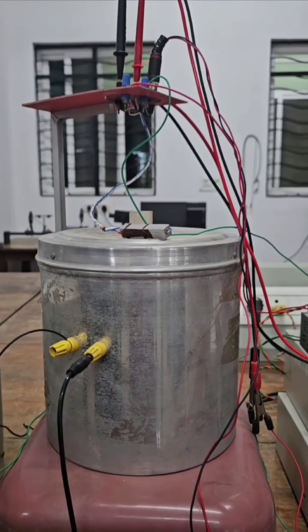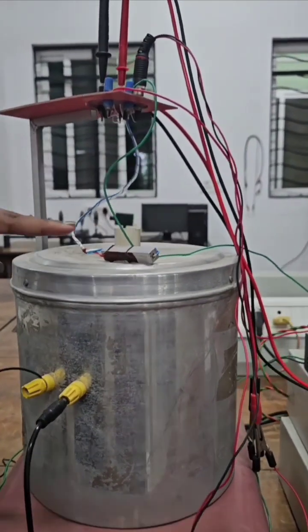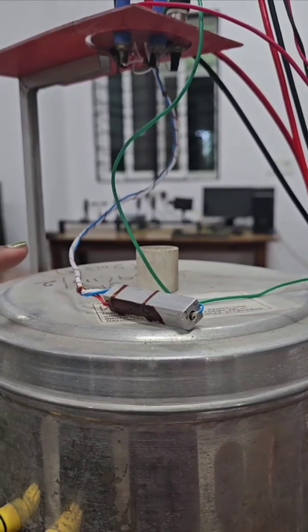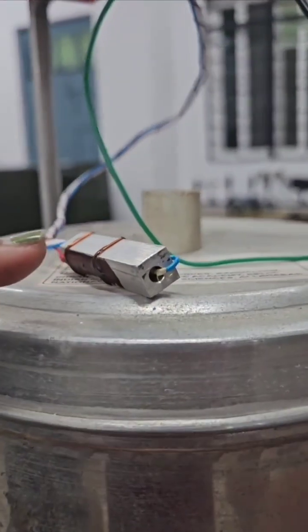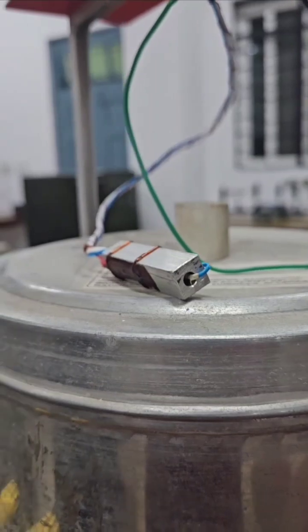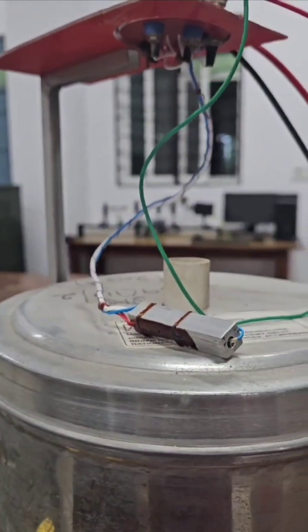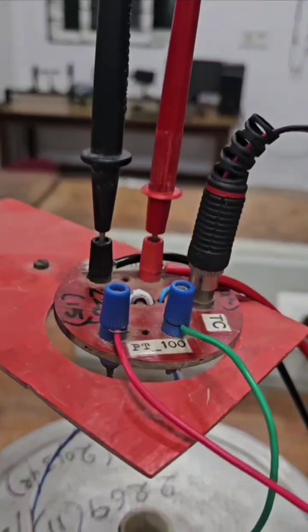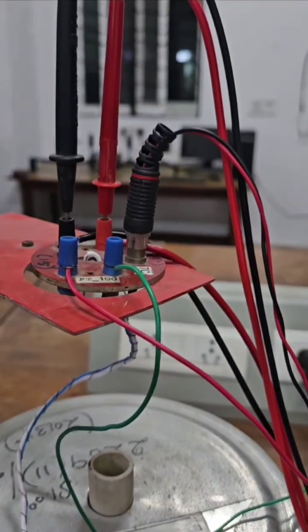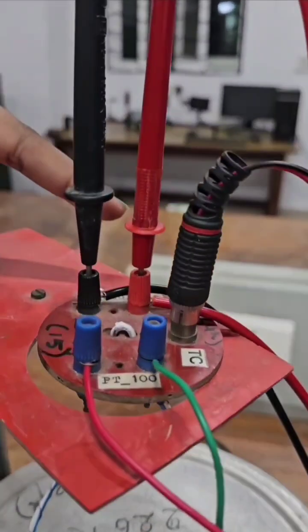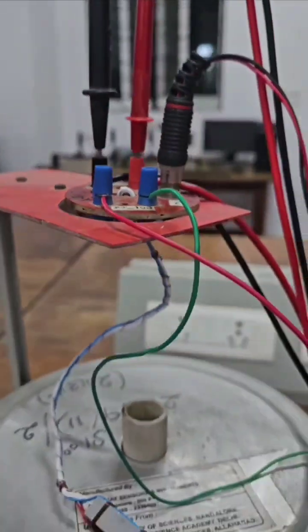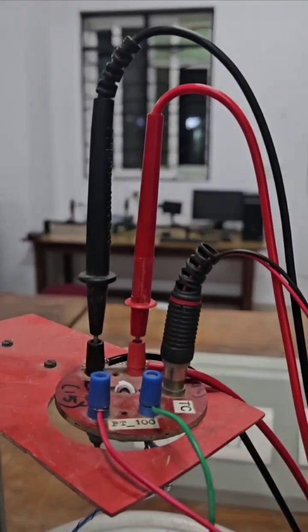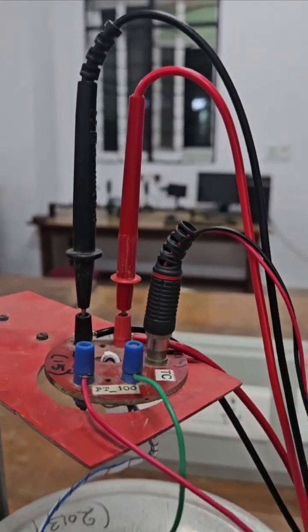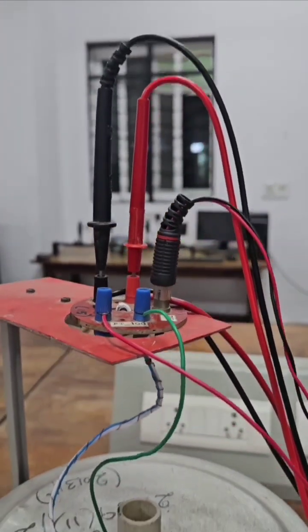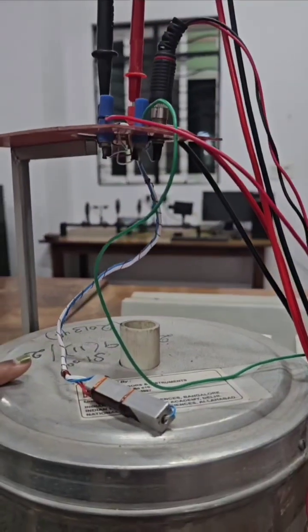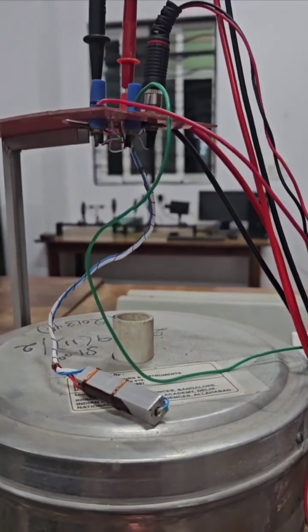So this is the furnace, and the furnace has an insert. This is a length of aluminum rod of square cross section of 1 cm and an axial hole of 3 mm diameter is bored into the aluminum block. A PT100 sensor is inserted into the block, and on one of the lateral faces of the aluminum block the Si diode is fixed with araldite. Care is taken to see that there is no shorting of any of these elements with the block. The aluminum block is suspended inside the furnace from the terminal disc on a stand fixed to the furnace.